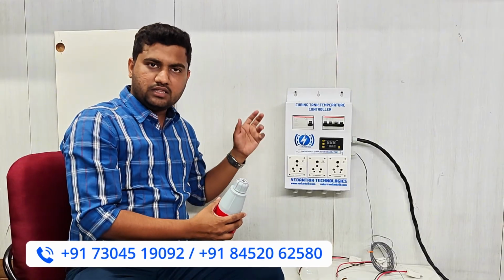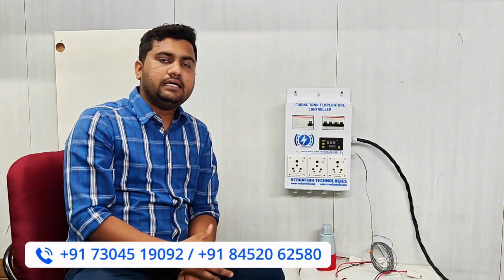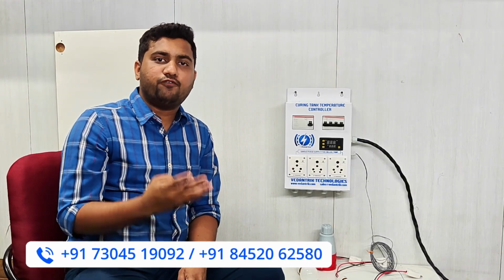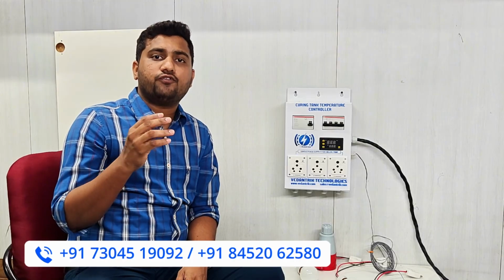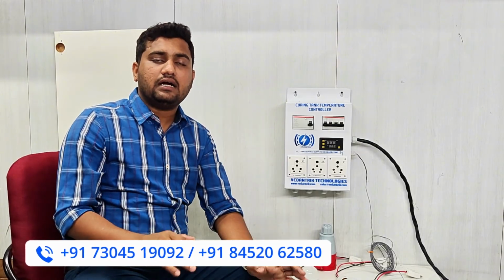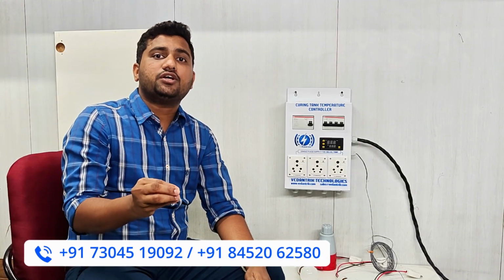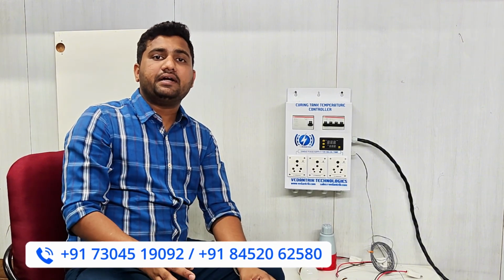I'll show you later in the video, there are 4 glands over here. So this type of 4 connectors will come out when you buy this type of controller which has both facilities, 3-phase and single phase. Now suppose you are buying 4 heaters of 3-phase and capacity of 4 kilowatt each. So you understand that 4 multiplied by 4 is almost 16 kilowatt heater. So 16 kilowatt heater is very much capable to easily maintain the temperature of 27 plus minus 2 up to 15,000 liters of water, right?